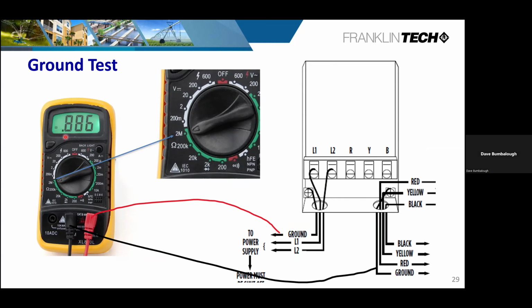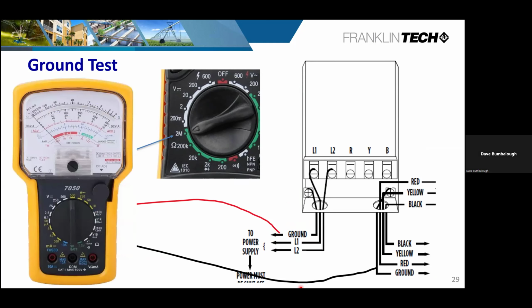You get up here around 886,000 ohms, something's wrong with the ground rods. It's more likely that it's probably a foot of ground wire or something of that nature. So you want to identify that and try to get that resistance down as low as you can. That's one of the things that I run into with the NEC. They're talking about putting a ground rod in, and if it doesn't measure under a certain value, you're going to add a second one, but then they don't give you any numbers to reference.